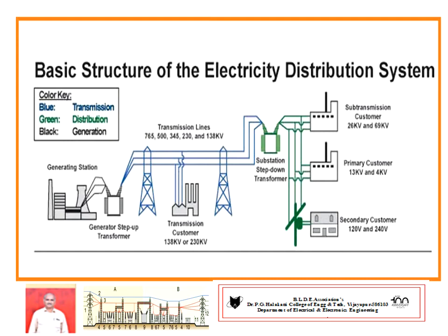The generated 3 phase power, 3 lines or 3 phases, is given as input to a step up transformer. It can increase the voltage level from the generating station, it may be 11 kV, it increases to 220 kV. 220 kV lines transmit the power. It is called transmission lines. Next, coming to substation, where voltage level can be reduced from 220 to 110 kV.